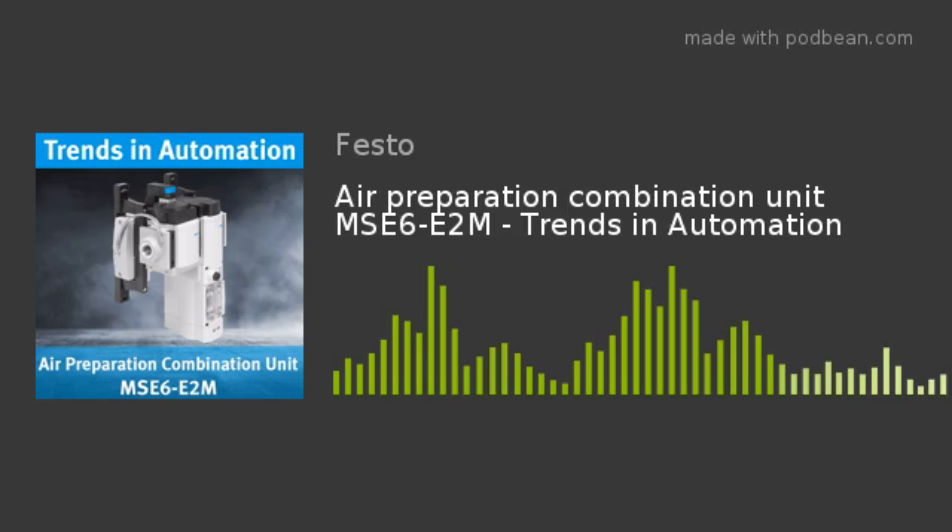The monitoring is in real-time. By providing real-time monitoring, operators have access to up-to-the-minute process-related data, as well as comparative data over time. Values for flow rate, air consumption, and pressure are continuously available. Comparative data can help personnel determine historical trends in consumption, the amount of air consumed per batch of product, and also provide pressure and flow values at the time of malfunction or bad product batch. Condition monitoring and energy efficiency are common themes for smart manufacturing and Industry 4.0, and the E2M easily addresses both.